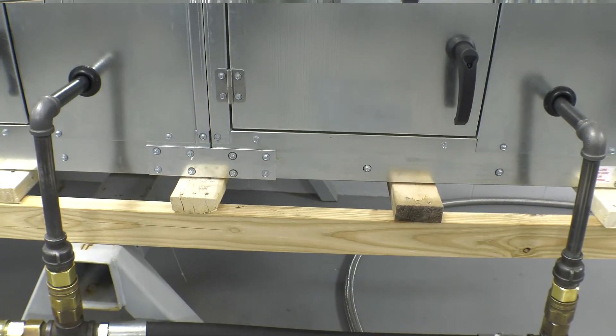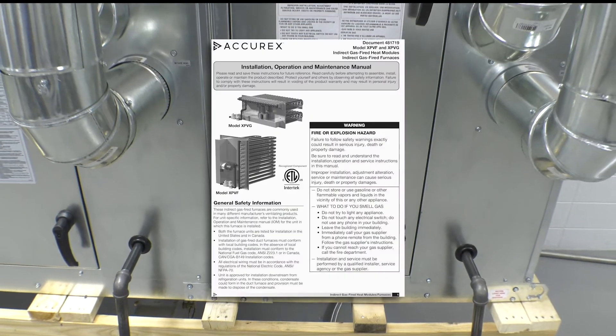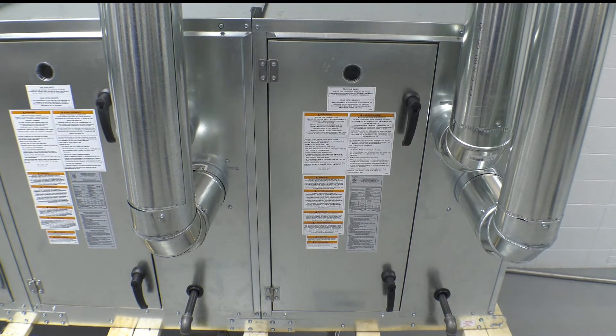Each furnace module is considered its own appliance and will require a separate gas supply line and needs to be individually vented if mounted indoors. Please refer to the XPVF XPVG IOM for further details on installing gas pipe and venting methods.